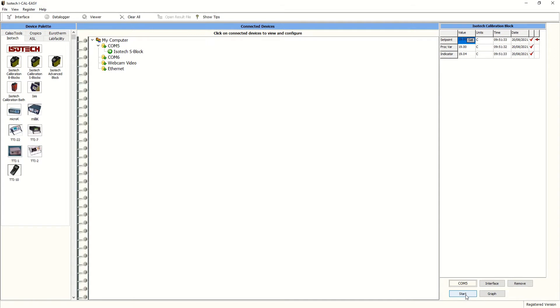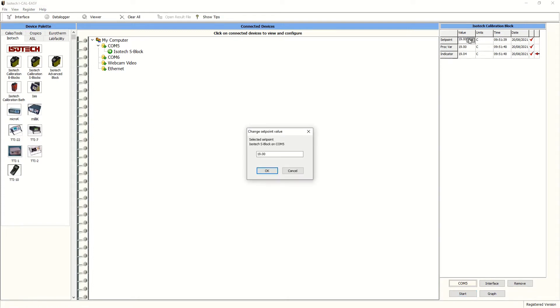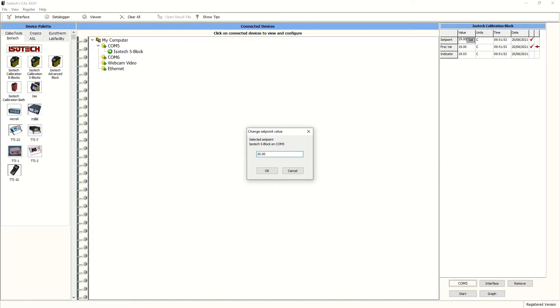And it's cycling through each of the inputs. Incidentally here, you can test the connection to the dry block by changing the set point. So we're currently at 19 degrees C and we can change this to 20 degrees C here within the software straight away. A useful function for most engineers.